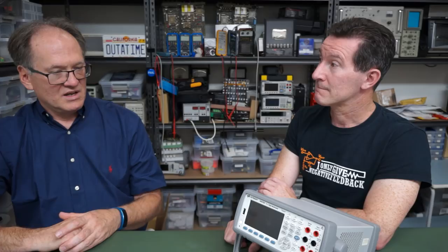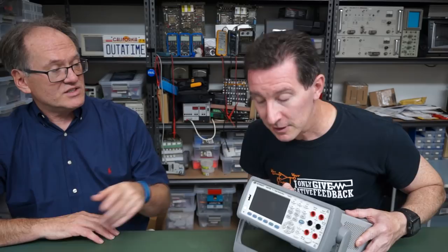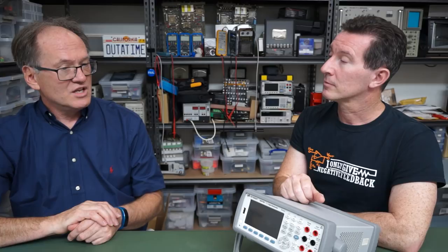The reference inside this and others. Are they getting difficult to get? No. So that's an interesting story. The reference that's inside the 3458 was developed by us 30 years ago. And we came to the conclusion that we're not the right people to make it. So we gave the design to linear technology. This is the LTZ-1000? Correct. You guys developed it. And we gave it to them. And we have a big burn-in system in our factory. That we mount them in little boards and we burn them in. And we sell graded versions for better results. Now the seven and a half digit one, this one, uses the LTZ-1000. It's one of the things that allows us to get to seven and a half digits. Because the drift. This doesn't have all the hooks that a 58 has. It doesn't have the level of Cal. It doesn't have the AC measurement technology that's unique on the 58. Some of that stuff is more straightforward. We had already started to work on redesigning that and stay tuned. We're in the process of looking how to take things to the next level.